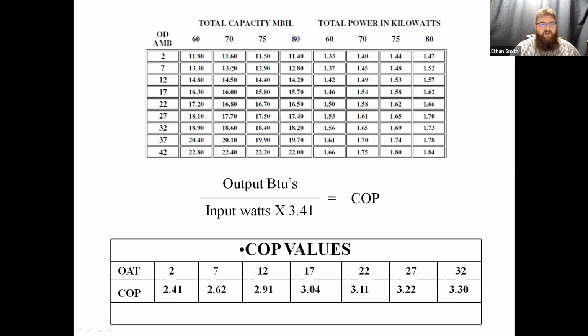And we took our output BTUs, which again, we went over to the 70-degree mark for our indoor temperature. At 2 degrees outdoor ambient, this unit's producing 11,600 BTUs, and it's doing it at a cost of 1.4 kilowatts. So we take those numbers, we plug them in for the output BTUs and the input watts, and we get a COP. So at 2 degrees, my COP for this system was 2.41, at 7, 2.6, and so on and so forth, all the way up to 32 degrees. And you can take this further if you want. With my current system, I actually had to take it up to 40 to find my break-even COP.